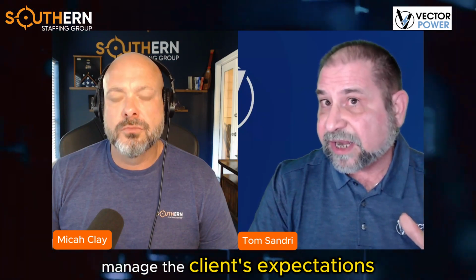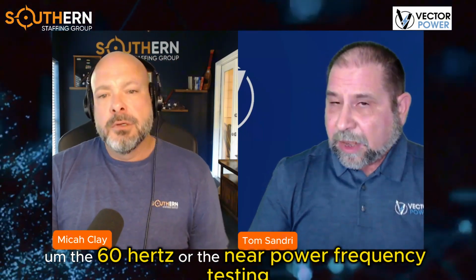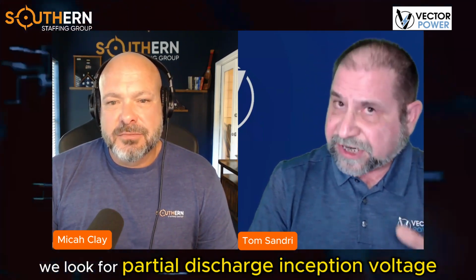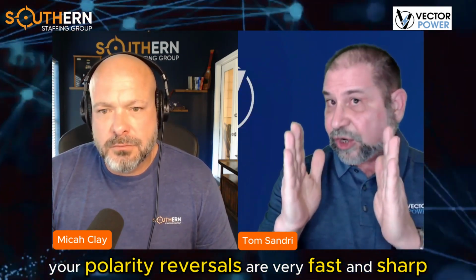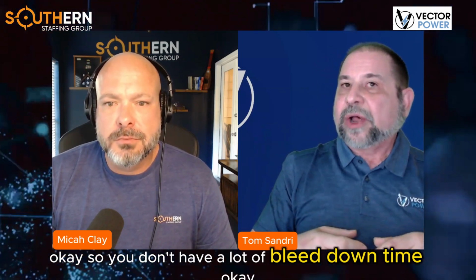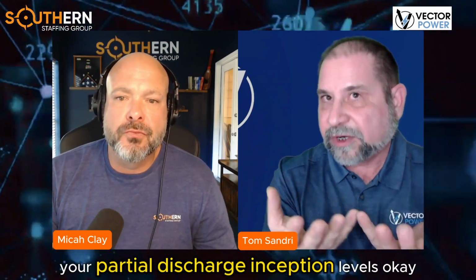Manage the client's expectations. Sometimes we don't tell the rest of the story, like only wanting to do 60 hertz or near power frequency testing because part of the test looks for partial discharge inception voltage, how much voltage it takes before PD is actually produced. The only accurate way of doing this is at 60 hertz, since that's how it reacts under normal factory operation. There's a tremendous amount of truth to that. At 60 hertz your polarity reversals are very fast and sharp, around 4 millisecond timelines, so you don't have much bleed-down time, you go from 0 to full charge quickly. That gives you a good perspective of your partial discharge inception levels.